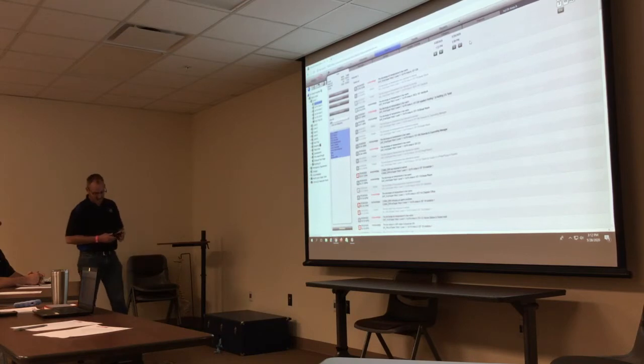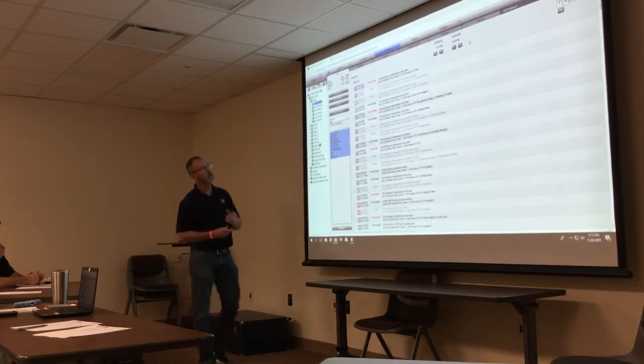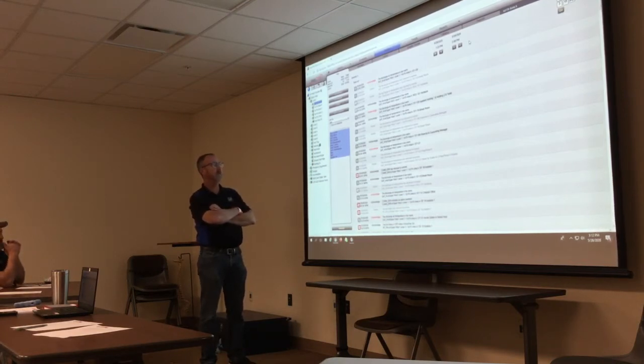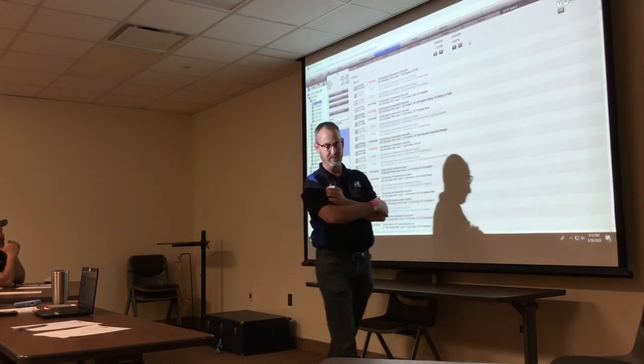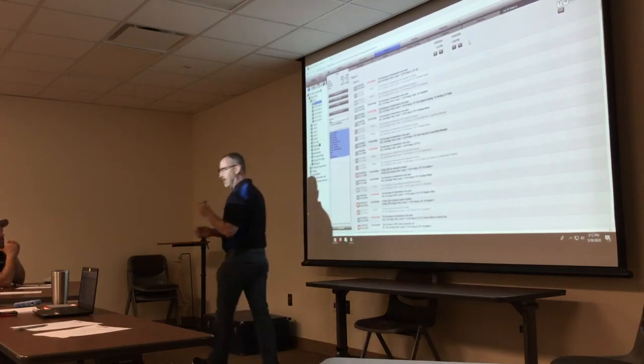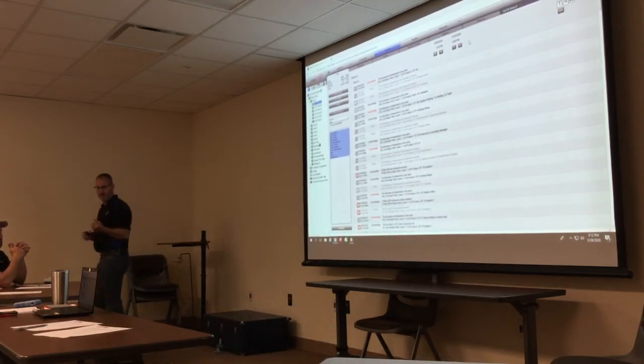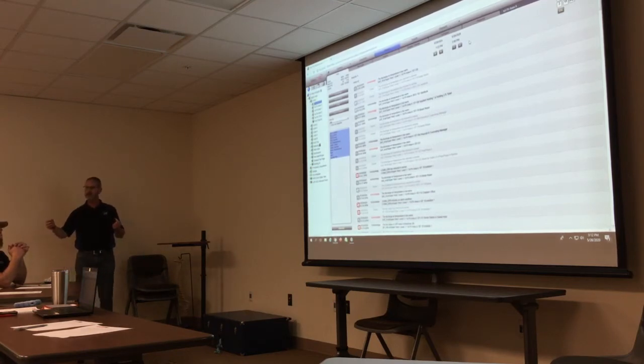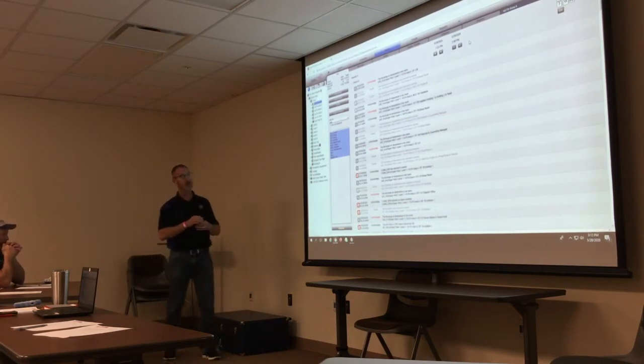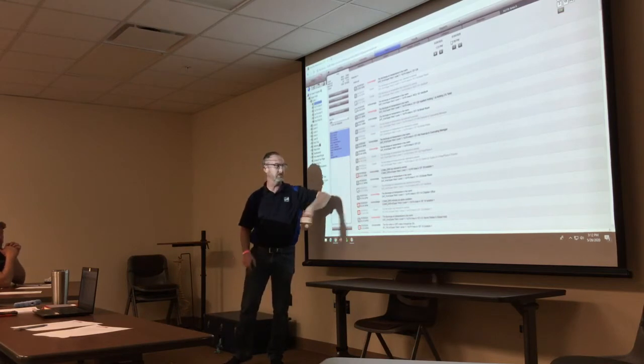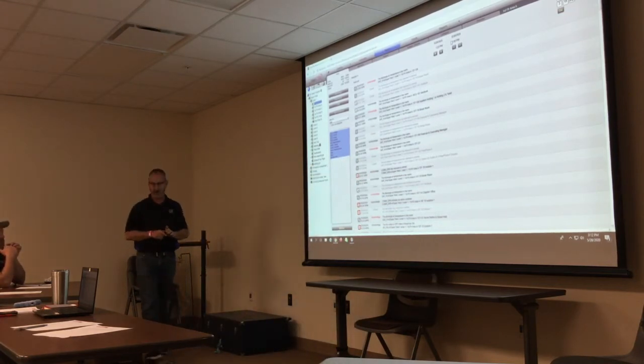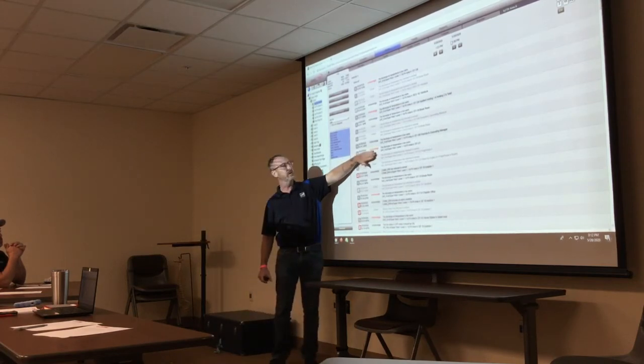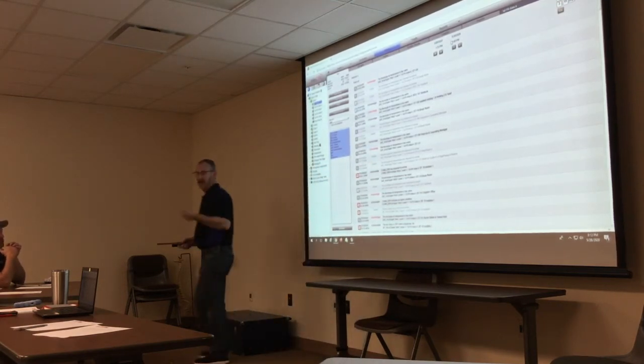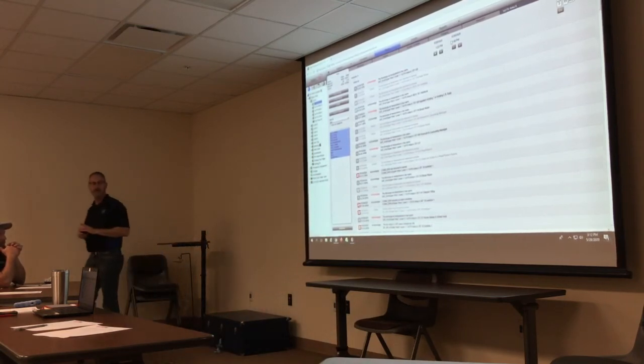How long do those remain? So they actually remain, I'll have to double check. I think right now I've just got them remaining 7 days after they've been acknowledged and returned to normal. So two things have to happen for them to get deleted out. Somebody has to acknowledge that there was an alarm, and that alarm has to return to a normal state. That either means you go and fix it to return it to a normal state, or if you say had something like a discharge air temperature was high here, and it returns to normal when the heating valve closes, then it'll acknowledge it will return to normal. And the text would go from red acknowledge to just a black acknowledge. So red means it's still actively an alarm. Black means it's no longer an alarm.